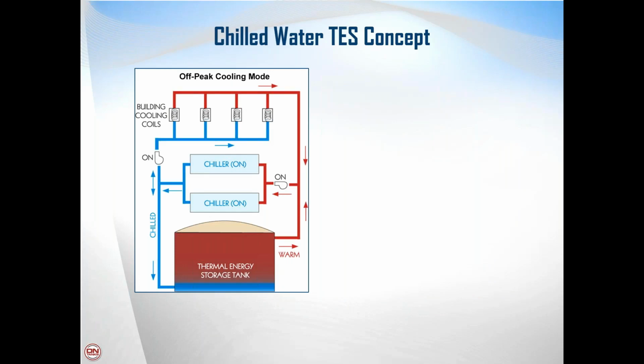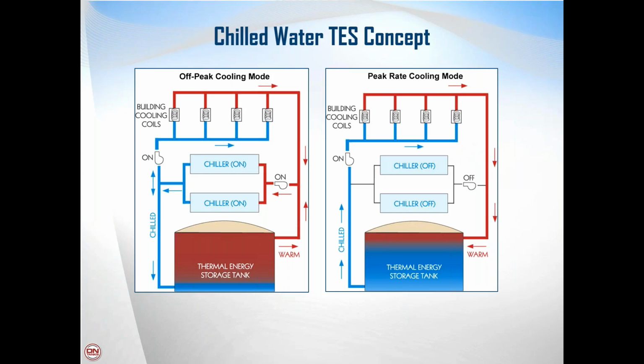Well, let's look at how a typical system would operate. This is a schematic of the typical chillers in a central plant. They're turned on during off-peak hours. They're producing cold water, which you see in blue, and that water is cooling the campus while simultaneously charging up or providing cold water to that thermal energy storage tank. Then during peak hours, the chillers, either one or more of the chillers, are turned off, and that cold water in the tank is drawn out through a pump, and it's pushed into the campus for cooling the campus. So that energy that's been stored in that water is now provided to the campus, and the warmer water returns back to the thermal energy storage tank.